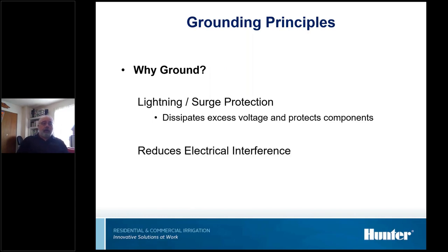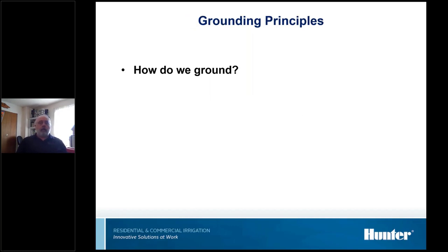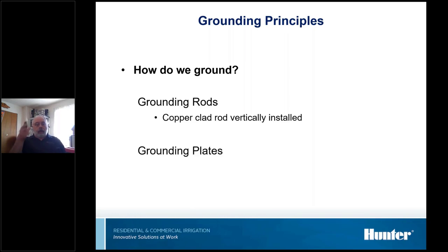The other thing it does is reduce electrical interference. It's not a huge deal compared to what it does with surge protection, but grounding controllers and grounding the wire paths definitely helps with noise problems. So how do we ground? Basically, there are two different ways we ground. We either use a ground rod, which is a copper clad steel rod, and they're installed vertically. In other words, we're going to just pound it straight down into the ground. And the other one is a grounding plate. Grounding plates are horizontally installed. It's a copper clad plate.